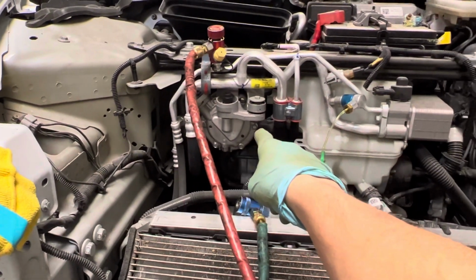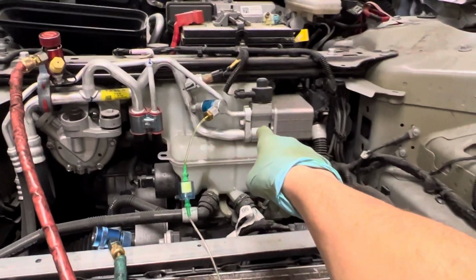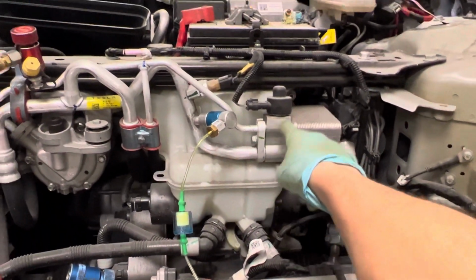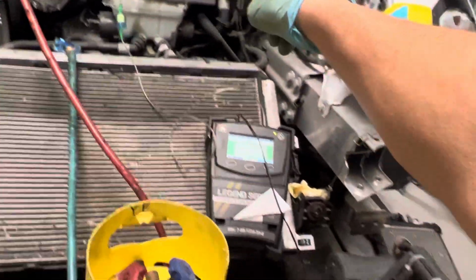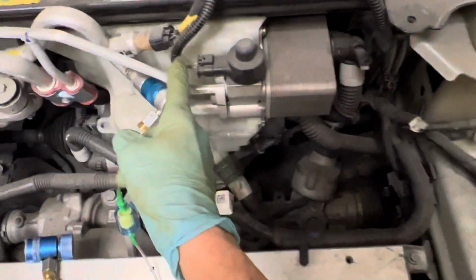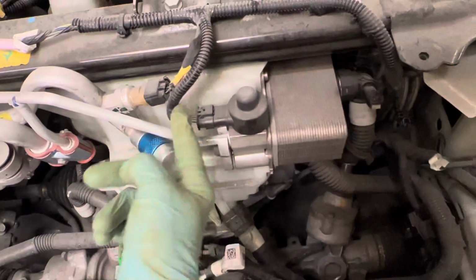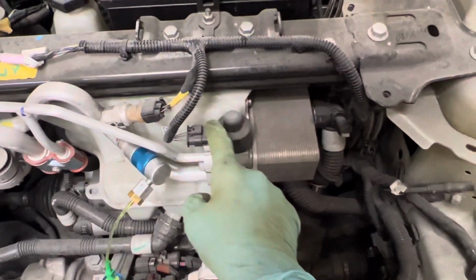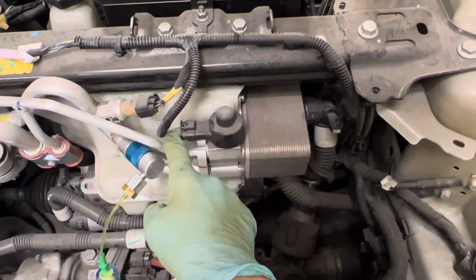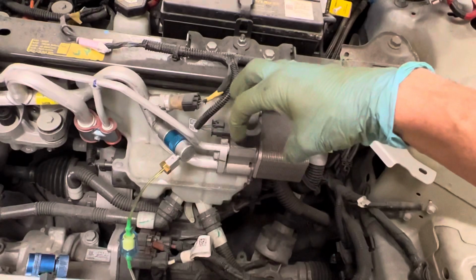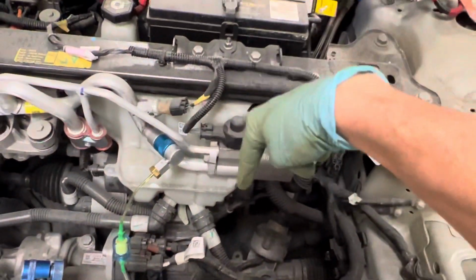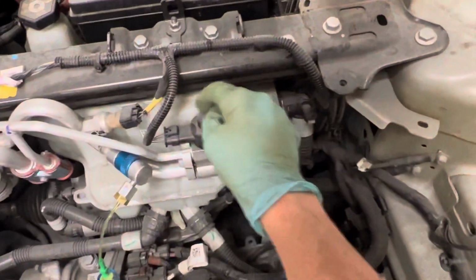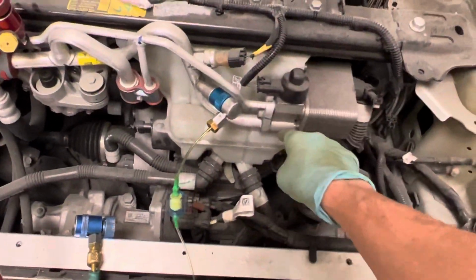There's your electric compressor. What's that? Expansion valve. What's that? Electric expansion valve. A 4-wire sensor. I didn't read anything about this, there's very little information about it, but I don't have to. We have a 4-wire connector, so we'll likely have position sensors, with a step actuator or stepper motor moving the pintle up and down, and a sensor array that senses what position it's in. So here's our electronic expansion valve.